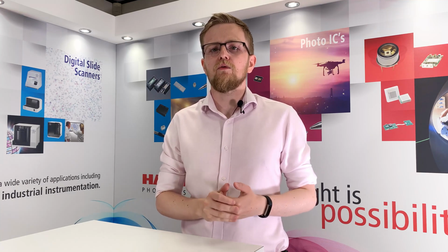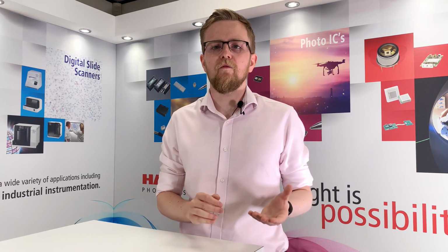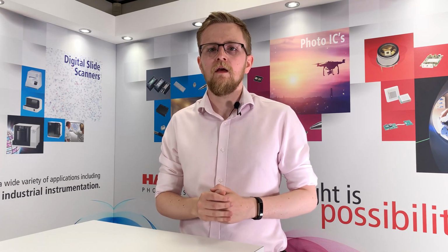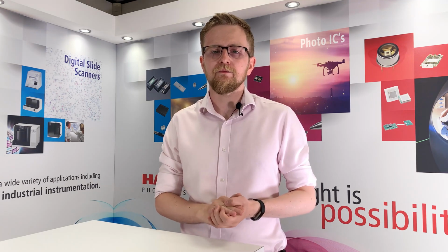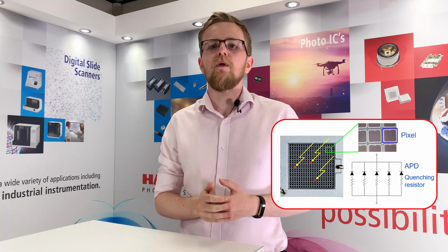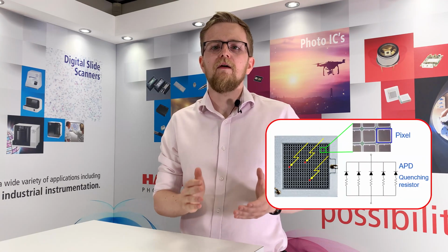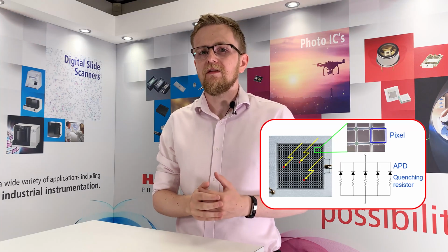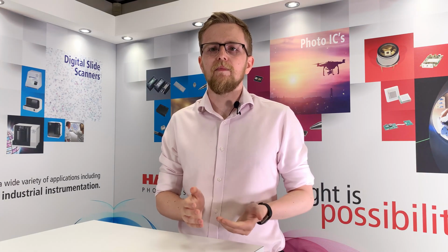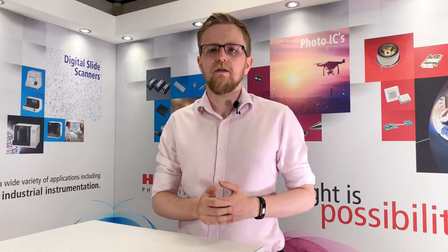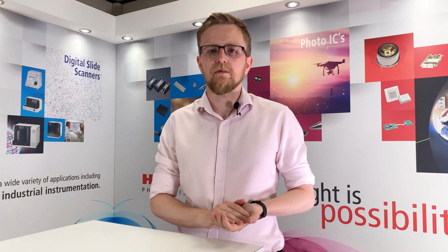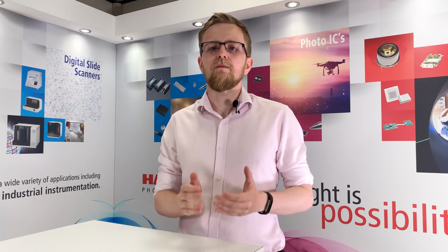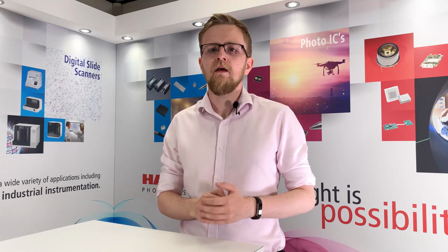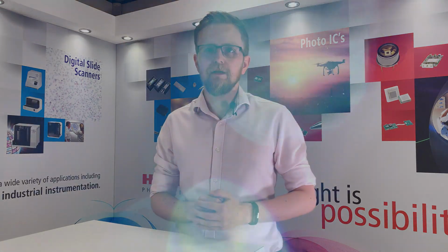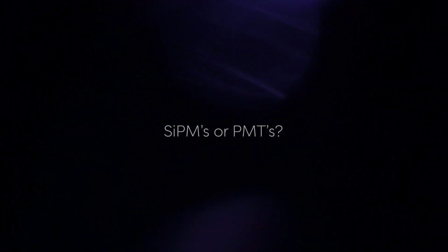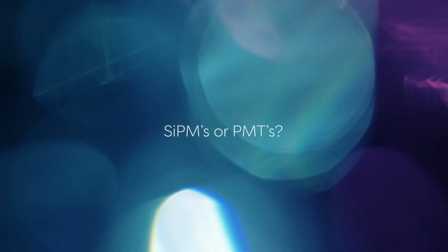Changes in the amplification circuitry surrounding PMTs, such as the move from vacuum tube circuits to transistor-based circuits, improved the performance to what it is today. More recently, arrays of silicon avalanche photodiodes paired with quenching resistors have been fabricated into multi-pixel photon counters, or MPPCs, which are more commonly known as silicon photomultipliers, or SiPMs. As this technology improves, it is proving a popular alternative to the PMT, especially in applications that require portability. SiPMs or PMTs?